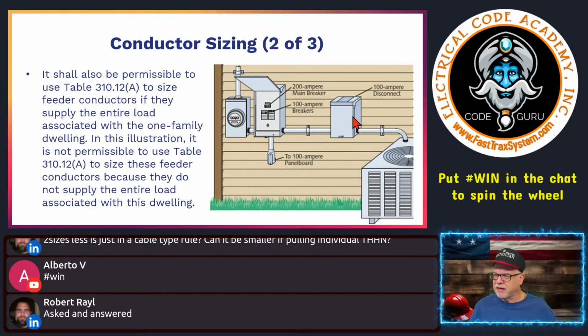here, okay? Now, interesting. These right here, since these are not feeding the entire load, you know, this right here, disconnect, this right here is feeding the entire load. This would be fine for 83%. This is just an example where these would not. Could not use the 83% on these. So these would be full-sized, okay? Full size to the 100 amps, okay?